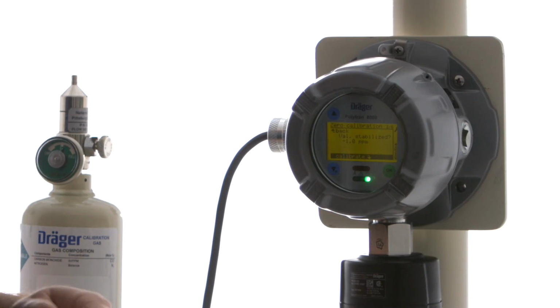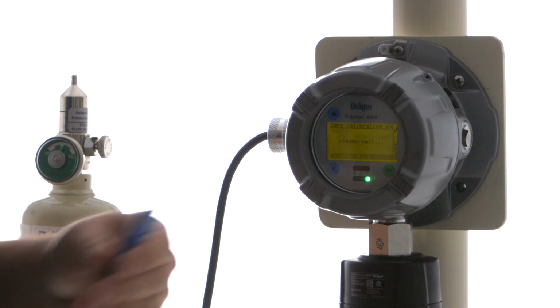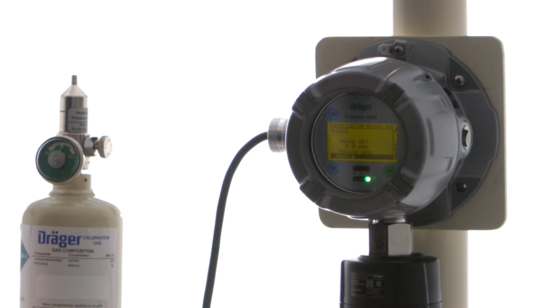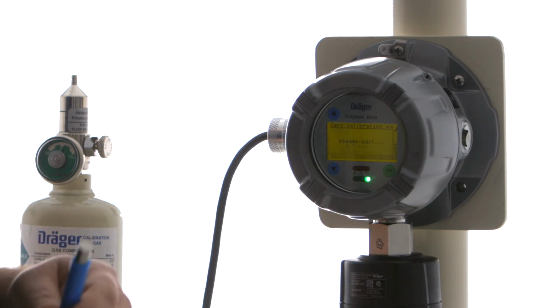At zero calibration with a Polytron 8000 series of devices, or in this case specifically Polytron 8100, you really only want the value to stabilize. It's not necessarily going to go to zero. You're not necessarily looking for a 0 ppm value. You just want the value to stabilize. We've stabilized at -1 ppm, and we simply go ahead and hit calibrate. The device now has a new value of 0 ppm. It's telling us to remove the gas if we had any gas, and we're going to hit next.